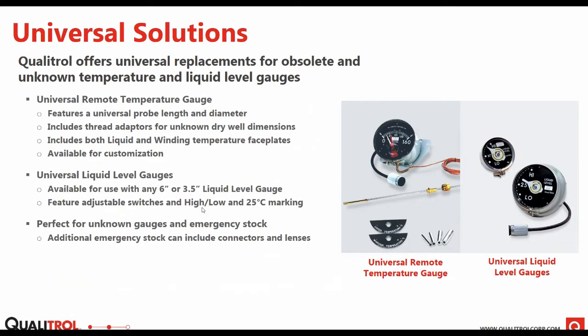So what we can do to help with replacements or emergency replacements are universal solutions. We have a couple of different universal options, mainly in our remote temperature gauges and our liquid level gauges. Our universal remote temperature gauge, which you can see on the right here, features a universal probe length and diameter, and includes thread adapters for unknown well dimensions and well threads. It includes both a liquid and winding temperature faceplate, and these can be customized. So if you need a different dial range or only want one faceplate, we can do a full configuration on that and still give the universal probe and thread adapter option.